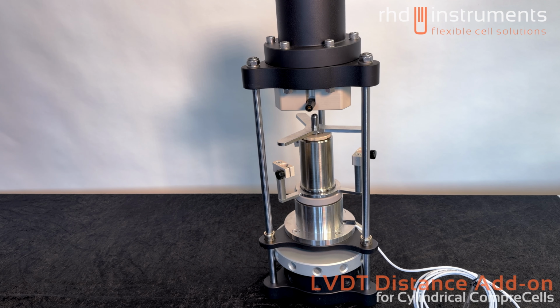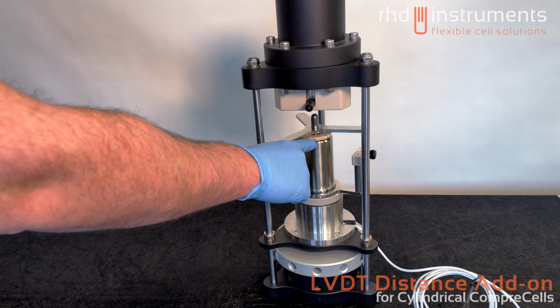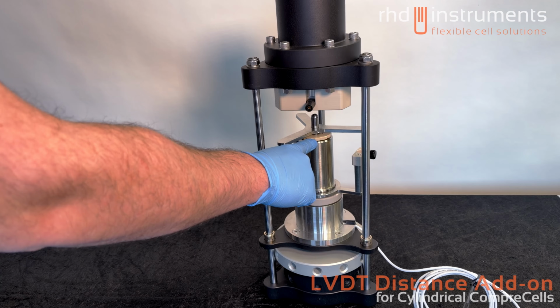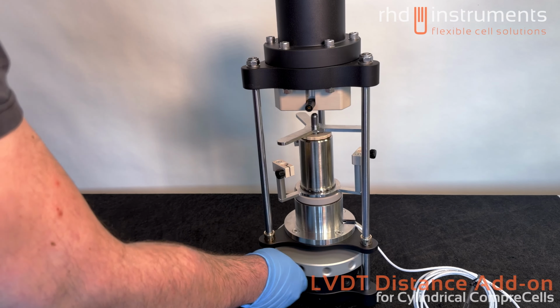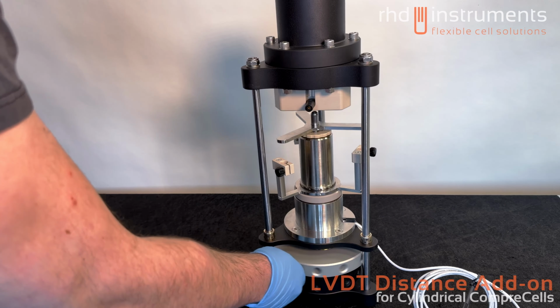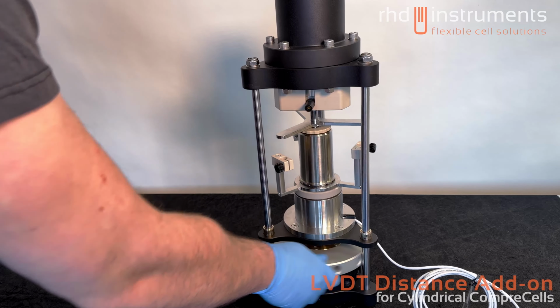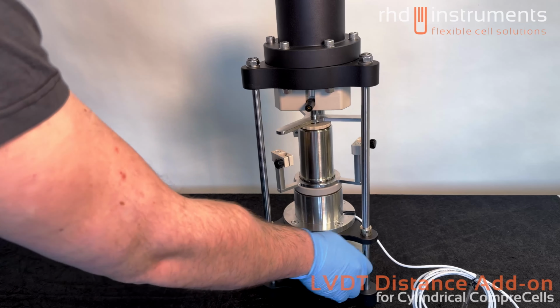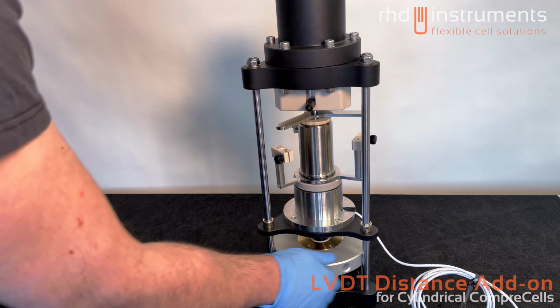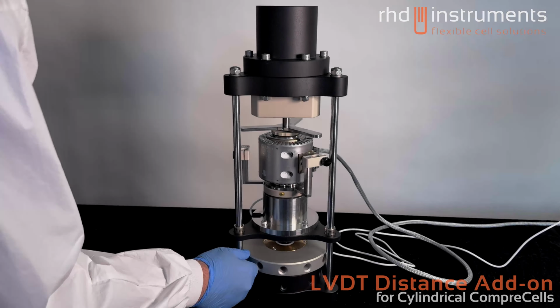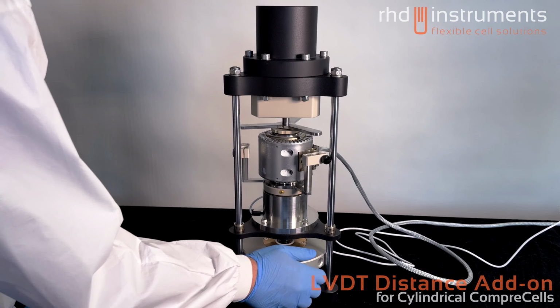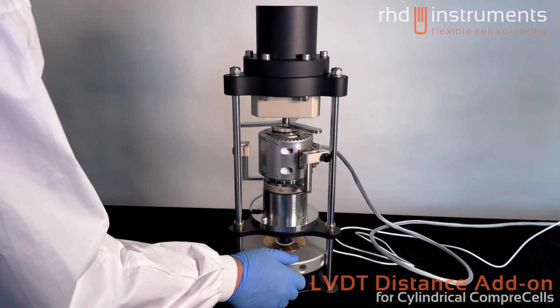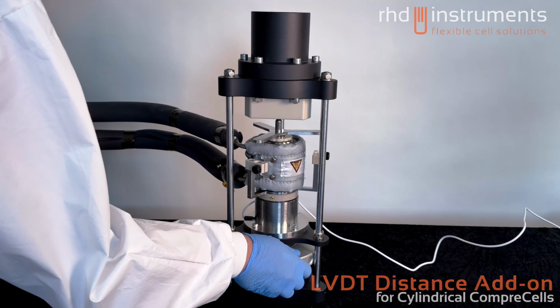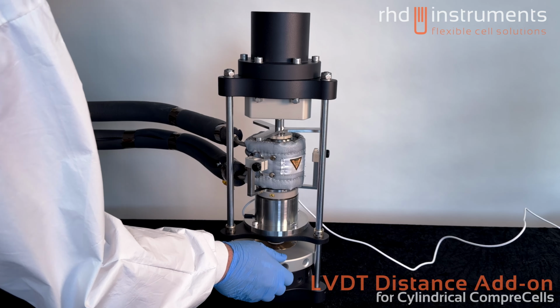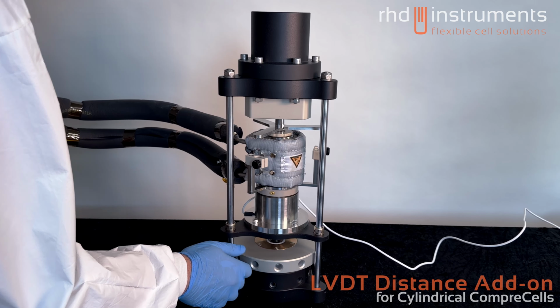If you are using a CompreFrame instead of a CompreDrive, there are only 2 differences. First, you will be using another lid because you need more clearance, and you have to do the first approach manually. Both CompreDrive and CompreFrame can be used with an H add-on and the LVDT distance add-on. Of course, it is also possible to use the distance add-on in the CompreFrame in conjunction with an HC add-on.